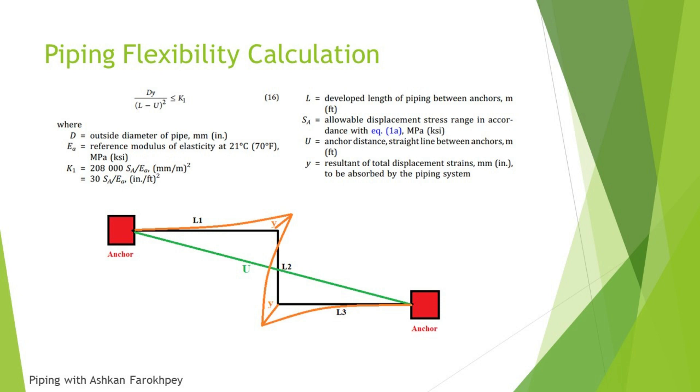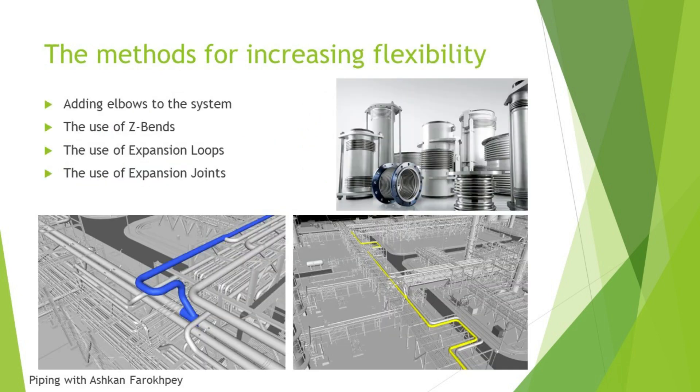Well, in these cases we have to use one of the four methods that I mentioned here. The first one is adding elbows to your system, like for example what you see in the left bottom picture. As you can see, the piping system could be run straight, but for controlling the thermal expansion it is turned and the length of the piping system is changed for controlling thermal expansion.